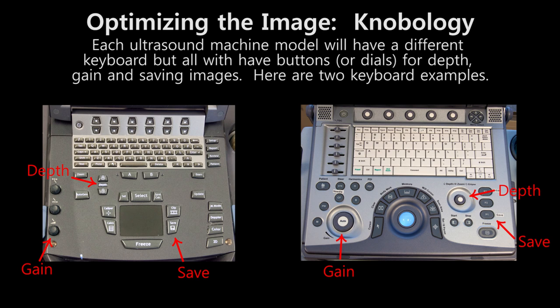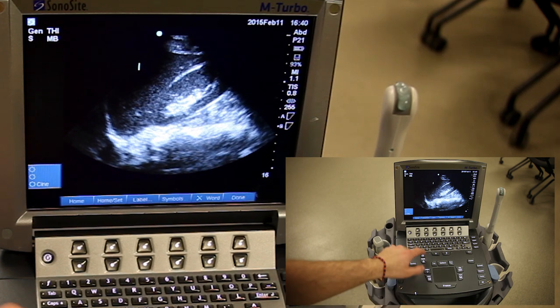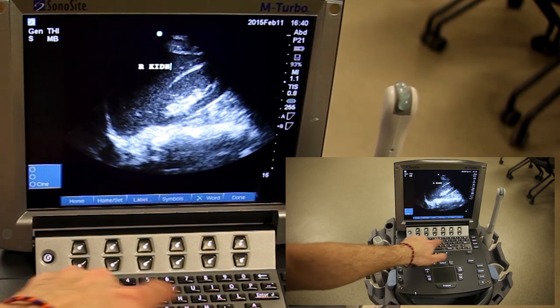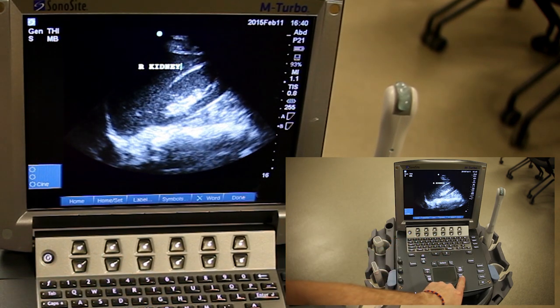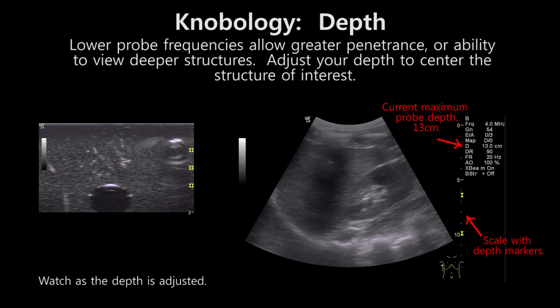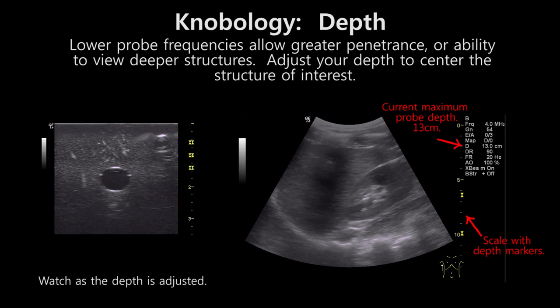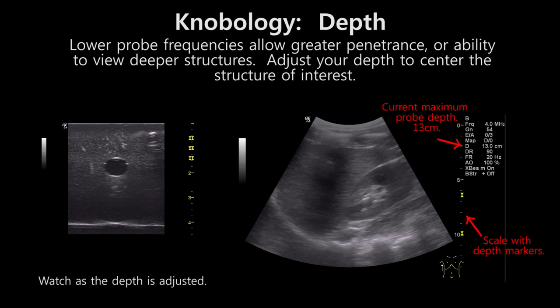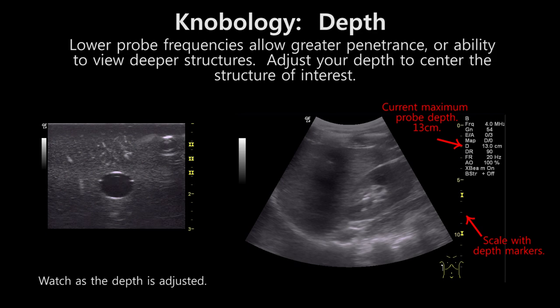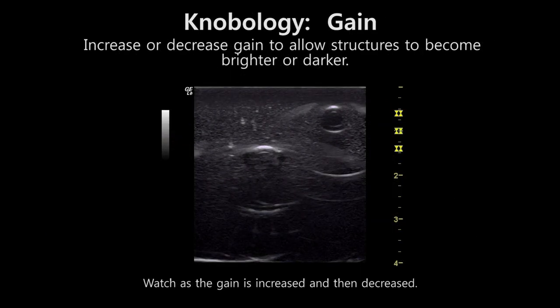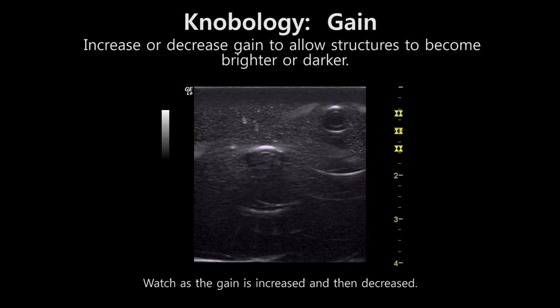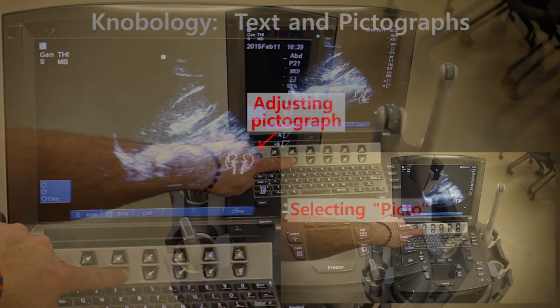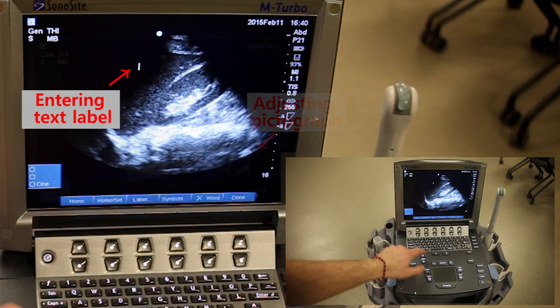Knobology. Once the tissue of interest has been identified, the image should be optimized by adjusting different parameters on the machine. The image should speak for itself, being of good enough quality that the structure being viewed is identifiable. Labels or pictographs should be used to help fully understand where the image was obtained, such as the left or right side of the patient. Increasing the depth allows for visualization of deeper structures. The proper depth setting is usually determined by what structure is being imaged and which probe is being used. Increasing the gain will amplify the reflected signal and effectively make everything brighter, though the downside is that this will increase noise as well as signal.